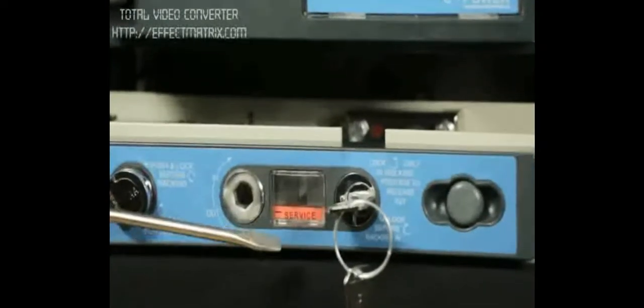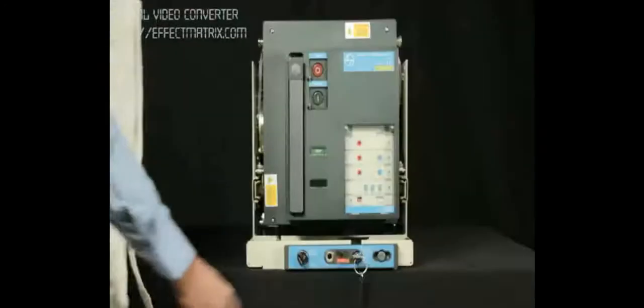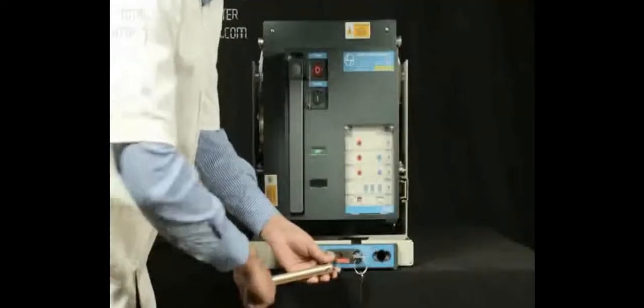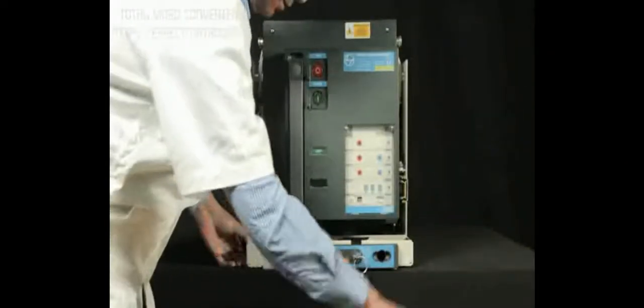Now breaker is in service position. Take out the racking handle from the cradle. Insert the handle in the slot provided for racking and rack out. Rotate it in anti-clockwise direction until breaker comes to isolated position.